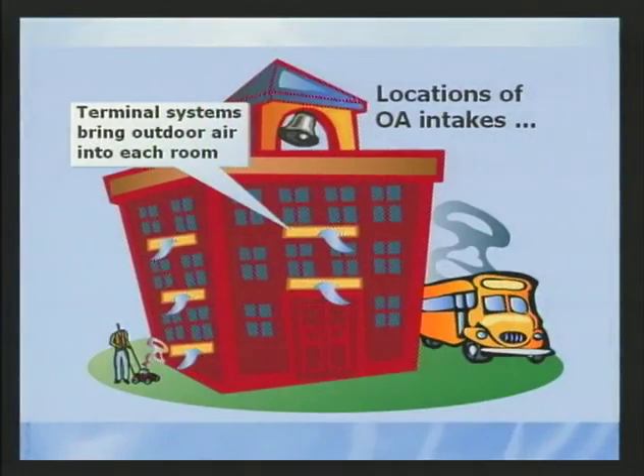Location of the outdoor intakes is important. Schools using terminal systems such as unit ventilators or wall hung units draw in ventilation air locally at each unit, typically near each classroom. This results in a high number of locations and thus many opportunities for entrainment of pollutants. Buses idling outside the school for extended periods of time, lawn care products or pesticides, or even microorganisms that may live in the landscaping immediately outside the classroom can all pose a problem.